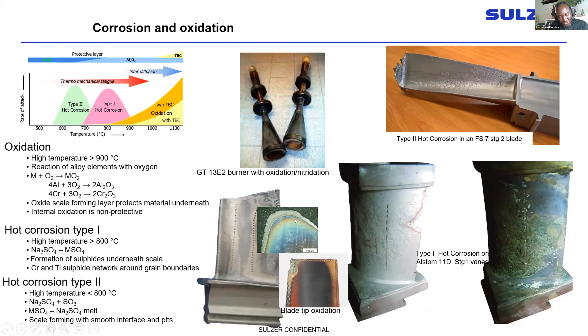This is due to overheating, maybe you're overfiring. Remember we talked about raising the firing temperature and all of that. So when the grid frequency goes too high and the machine is not properly controlled, you can have overheating on the combustion or turbine side. These are TBC coated frame 9E.